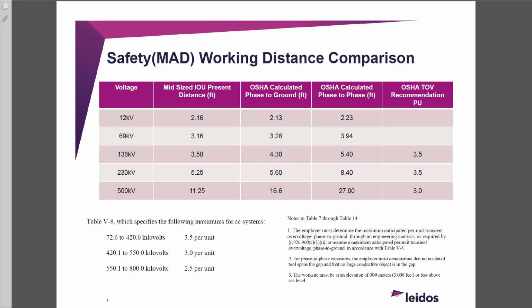If you look at the distance, this is a standard out of their safety book. We're not allowed to tell you which line, but this is their standard that they've used for the last 20 years. That minimum approach distance was 11 feet at 500 kV. When OSHA came through and made an assumption on what the TOV on these lines are, if you don't do a study using fancy software like EMTP, you have to use these assumed per unit values: 3.5 per unit on 138, 3.5 per unit on 230, and 3 on 500 kV.